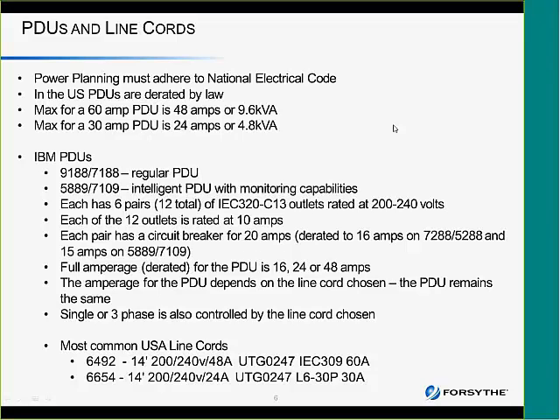The 5889, 7109 is the intelligent PDU with monitoring capabilities. All that means is it can report on what it's using. Each one of these PDUs has 6 pairs, so 12 total of IEC 320 C13 outlets, and they basically serve out 200 to 240 volts. And each of those outlets is rated at 10 amps.